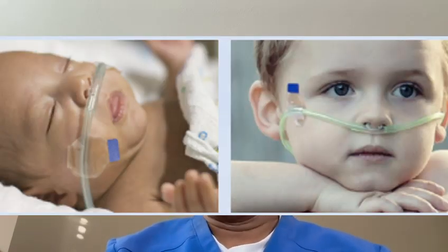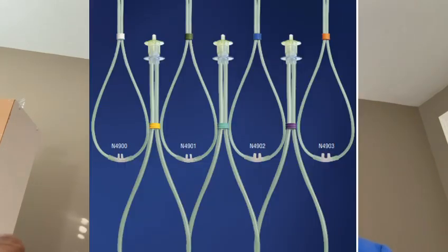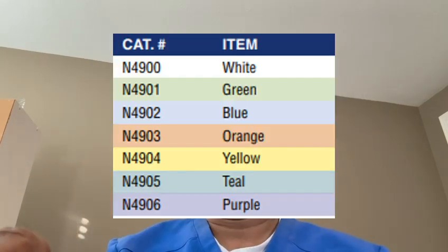Monitor for septal breakdown and check the position of the cannula with every shift or more often. Images show how it can be secured so the patient is comfortable, and also show neonatal and pediatric patients with RAM cannula in place. The RAM cannula is available in different sizes for neonates — micro preemie, preemie, newborn, and infant — all color coded. In pediatrics it is available in three different sizes, also color coded.